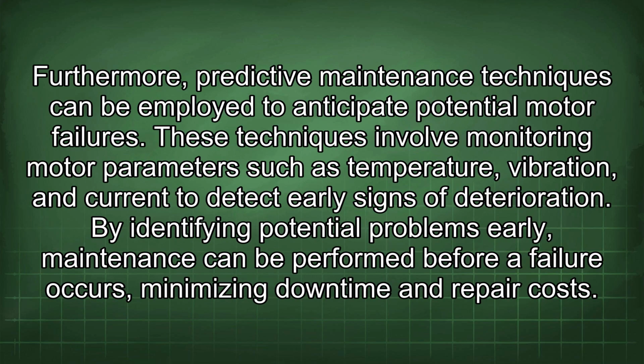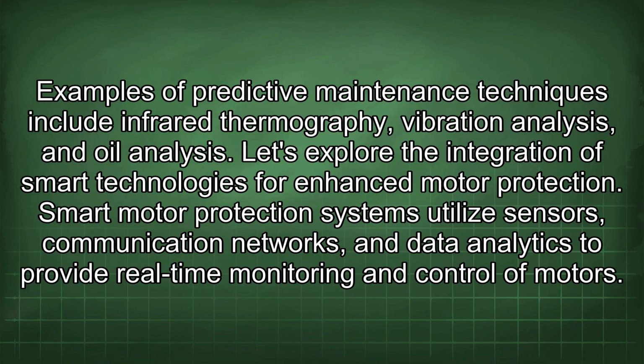Furthermore, predictive maintenance techniques can be employed to anticipate potential motor failures. These techniques involve monitoring motor parameters such as temperature, vibration, and current to detect early signs of deterioration. By identifying potential problems early, maintenance can be performed before a failure occurs, minimizing downtime and repair costs. Examples of predictive maintenance techniques include infrared thermography, vibration analysis, and oil analysis.